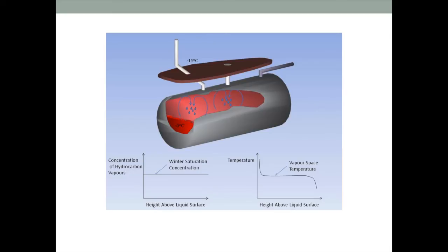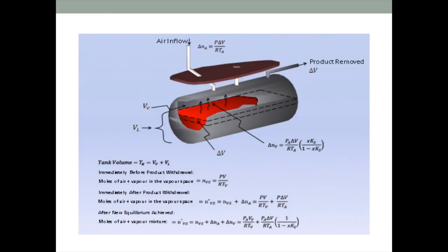What actually happens in a mass balance is: if you draw fresh air into the tank and promote product evaporation, then for every molecule of product that evaporates, you physically displace a molecule of air-vapor mixture from the tank. In a stratified condition, you're probably displacing an air molecule from the tank, which doesn't matter much. But in a well-mixed environment, you're displacing a molecule that is on average partly gas and partly air. Because we were seeing what appeared to be well-mixed conditions in the tank, we assumed full saturation in the vapor space and did our mass balance. You can solve that to get an equation that predicts evaporation losses as a function of activity on the tank.